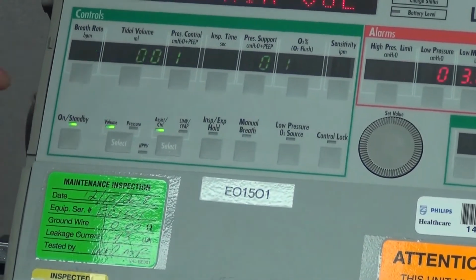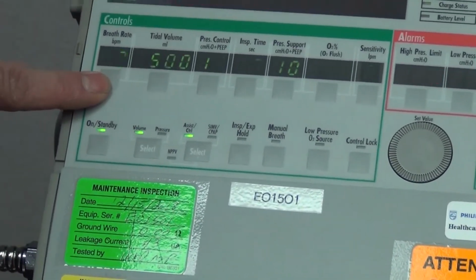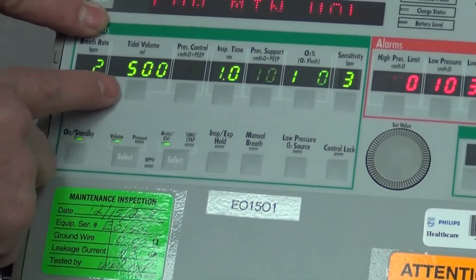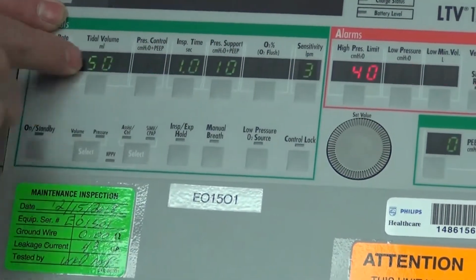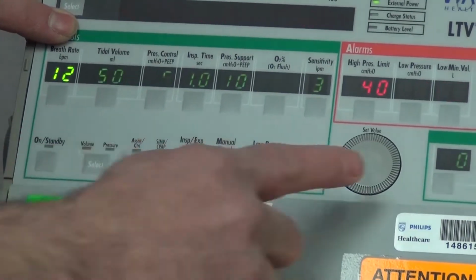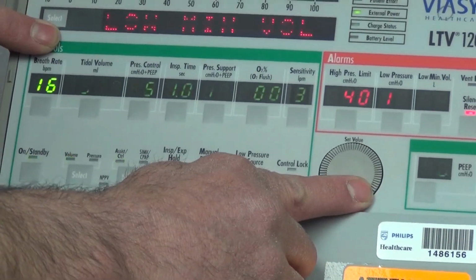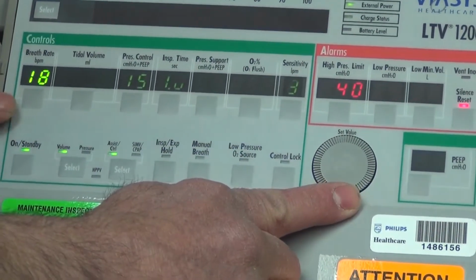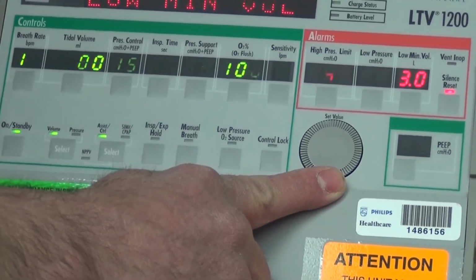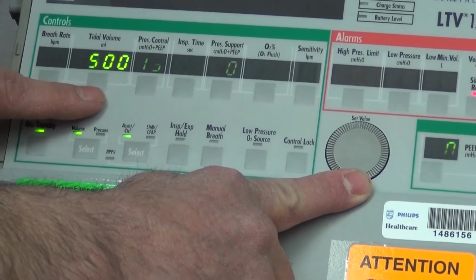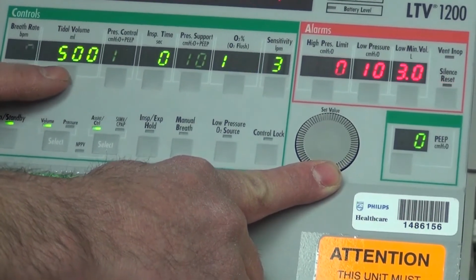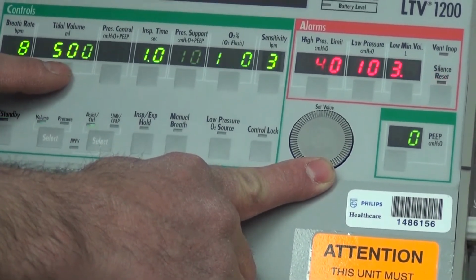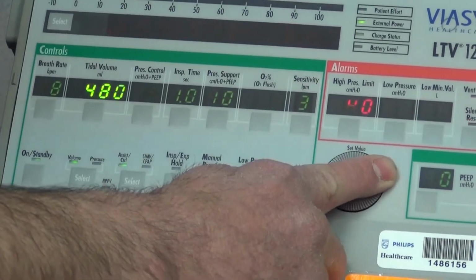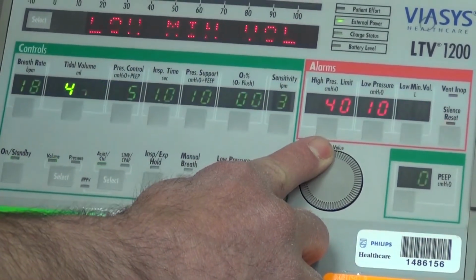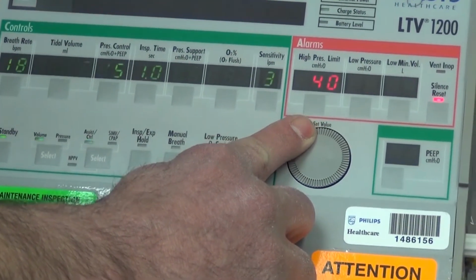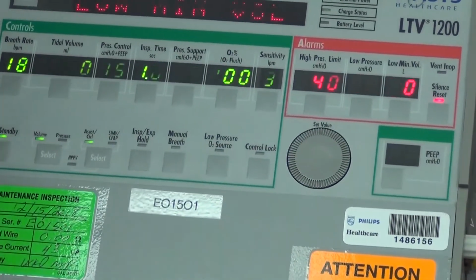So to select, notice I push this button underneath the breaths per minute, and the rest will gray out, as you can see. We're going to turn this wheel to set to 18, and then we're going to push it again to set it. Next, we're going to go to tidal volume. Again, these are settings you're going to get from the physician. You're going to hit that, and let's say we go to 450. There we go. And we're going to select.